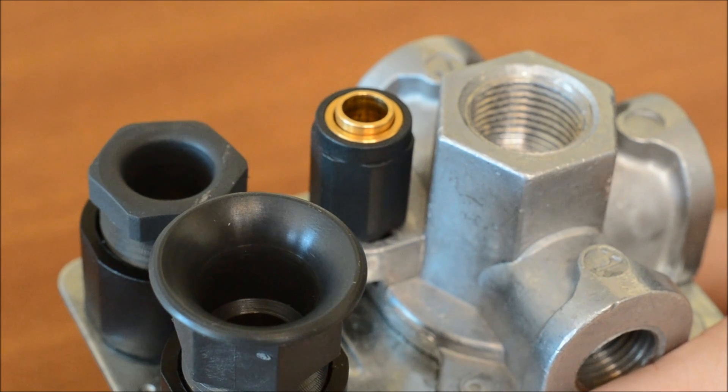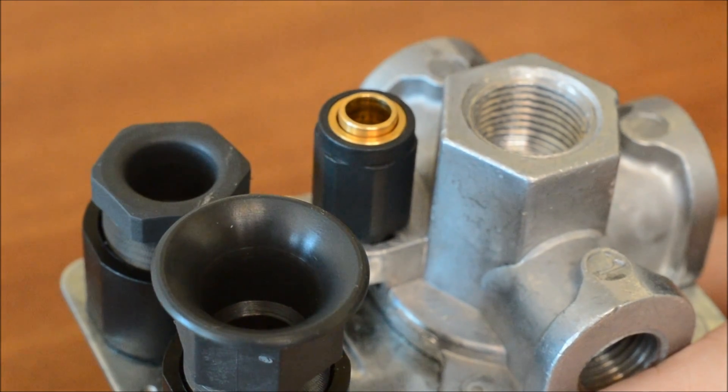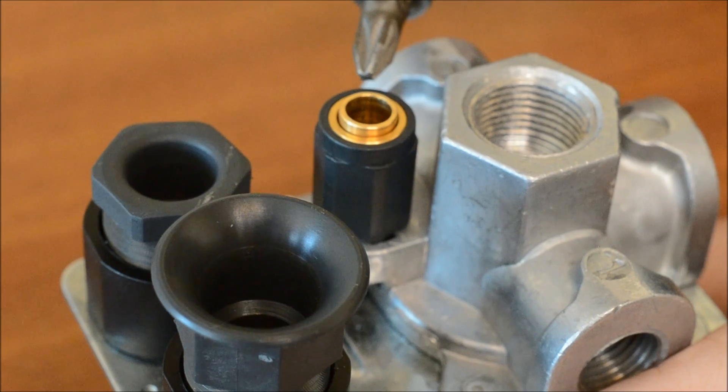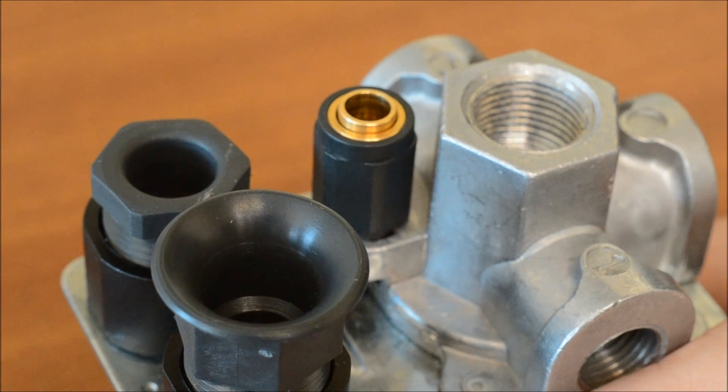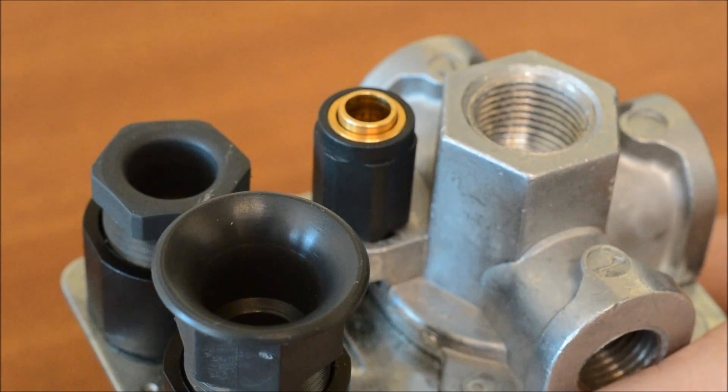The MDR1 is fitted with an unloader valve built-in, which has a 6mm push-in connection on the bottom. The purpose of the unloader valve is to remove pressure from the piston of the compressor and allow it to start without stalling.